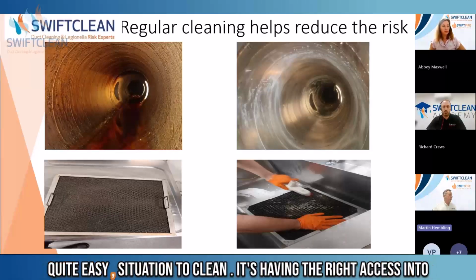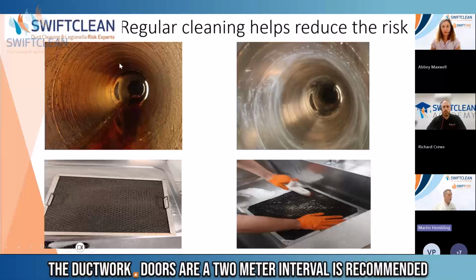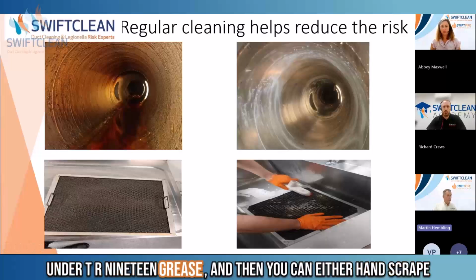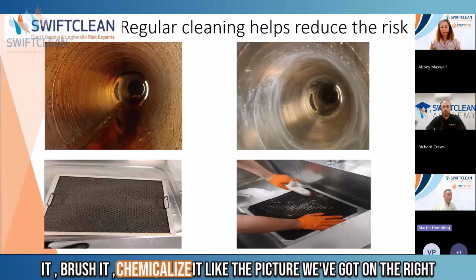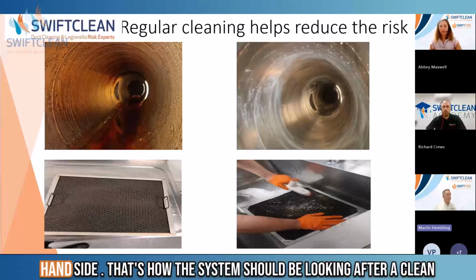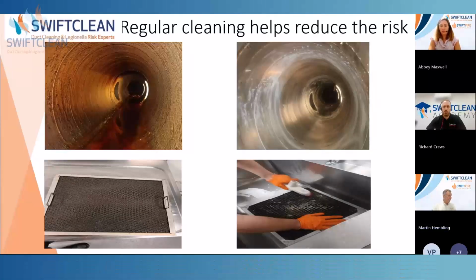So you need to remove it on a regular basis, and it's quite an easy situation to clean - it's about having the right access into the ductwork. Doors at a 2 metre interval are recommended under TR19 grease. Then you can either hand scrape it, brush it, or chemicalise it, like the picture on the right hand side - that's how the system should look after a clean.